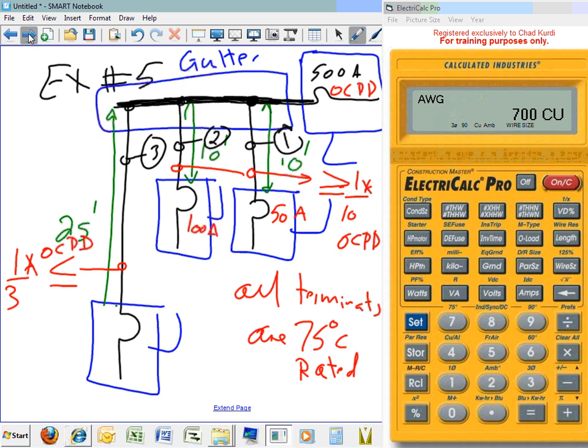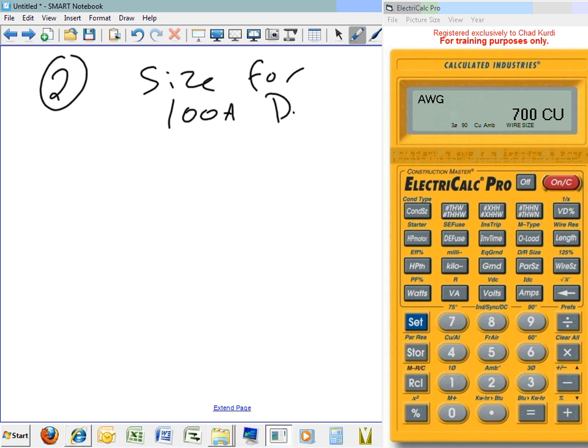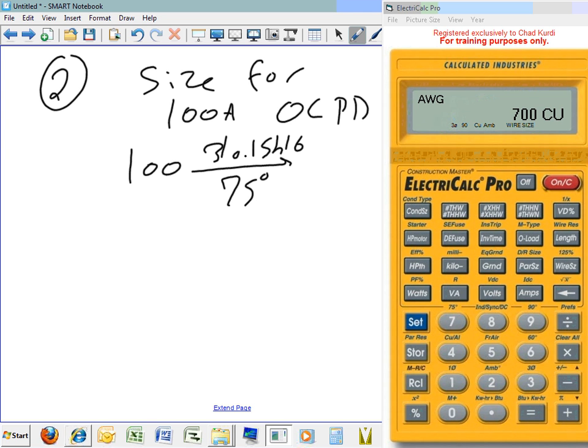So let's size that second one. Number 2. I said 100 amp disconnect, 100 amp overcurrent protection device. So you take the 100 to 310.15 B16, 75 degree. Why 75 degree? Because I'm telling you all the terminals are 75. What do you get? Number 3? Number 3. Thank you, sir. That will be 4 conductors, number 3.